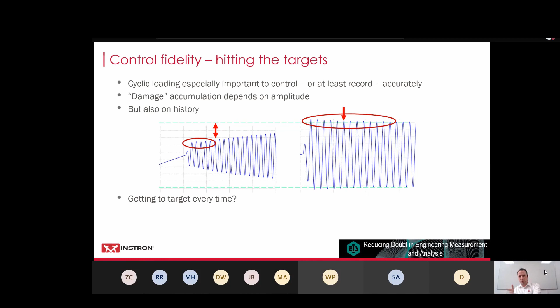Arguably worse, when we talk about those loading history effects, is if you've ended up a bit aggressive and you actually go over what you meant to, and you overshoot your target on the first few cycles. So with fatigue, particularly if you're doing aggressive loading intentionally, if you overshoot further, it can really affect the fatigue life of the specimen. It can affect the work hardening. So when you talk about control, you want to know, are you getting to the target every time?